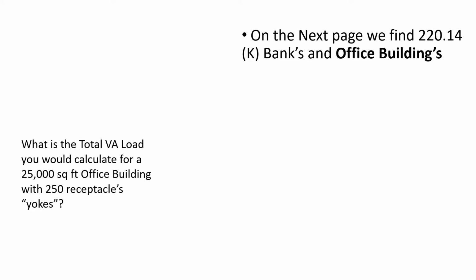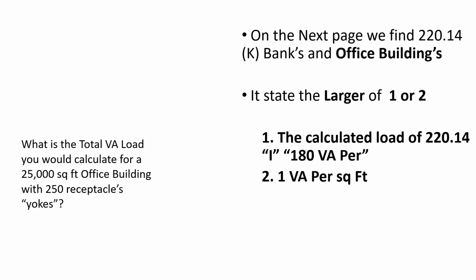Let's go ahead and flip to 220.14(K) for banks and office buildings. It's going to be on the next page from what you just read, at the top part of the page. It states that we must use the larger of 1 or 2. So it says the calculated load from 220.14(I), which is going to be 180 VAs per yoke, or 1 VA per square foot. Let's learn how to do that now.